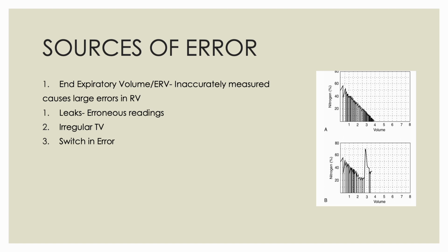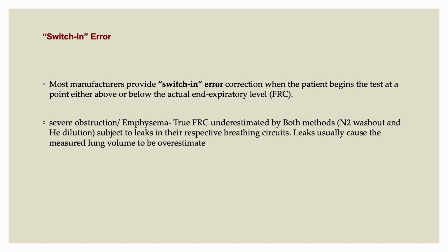The other thing is we're always starting with end of expiration. So ERV, if you do not calculate ERV correctly, the whole formula goes wrong. If there is a leak in the system, because we are assuming that there is no leak from outside, then the readings are erroneous. And if the patient's tidal volume is not regular, there may be changes there. Also, there is a special error called a switch-in error, when you actually open and close the valve, that can cause a problem.